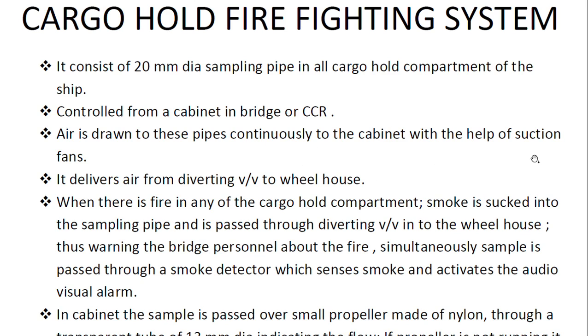The system delivers air from a diverting valve to the wheelhouse. The air sucked by the suction fan is delivered through the diverting valve to the wheelhouse or CCR — bridge and wheelhouse refer to the same location. When there is fire in any cargo hold compartment, smoke is sucked into the sampling pipe, passed through the diverting valve to the wheelhouse, thus warning the bridge personnel about the fire.